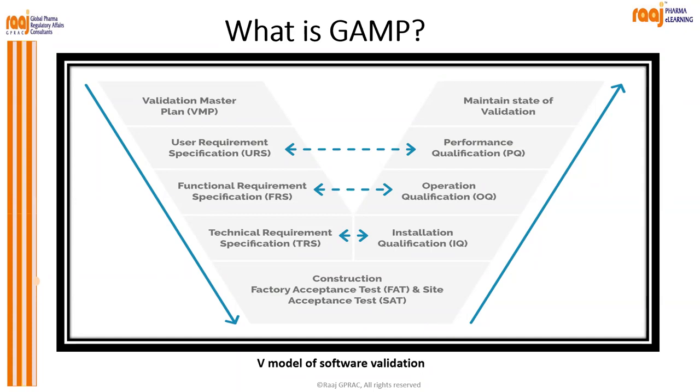If the machine is very huge, for example a compression machine, a fluid bed dryer, or anything else, just think about an X-ray machine or the CT scanner in the case of medical devices. When you dismantle each and every part and transfer it by courier, by surface or air, and it is installed again at your site, there are chances of it giving some haywire result, or some part is damaged during the transport or anything.